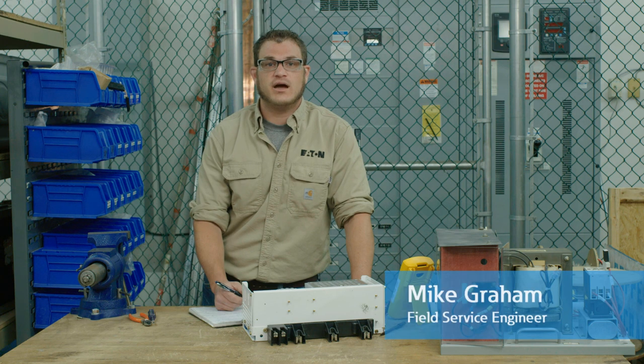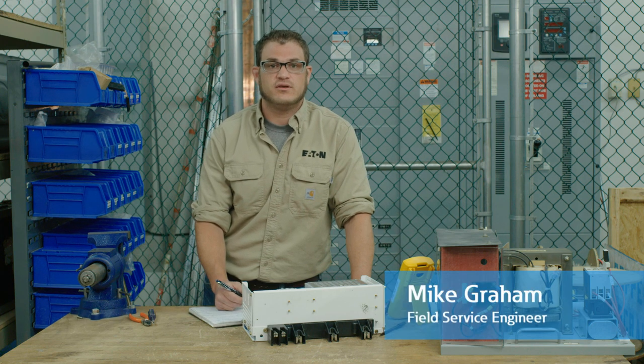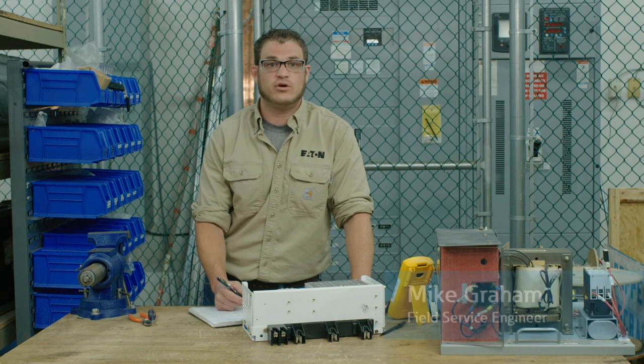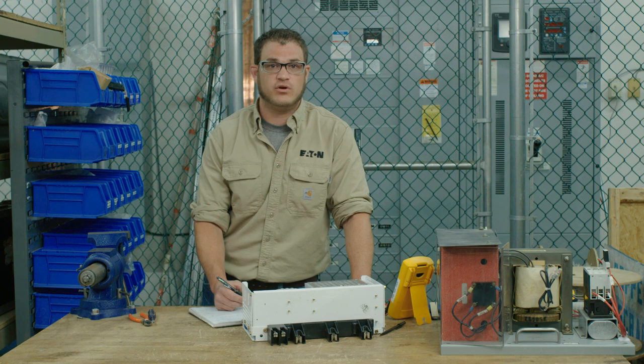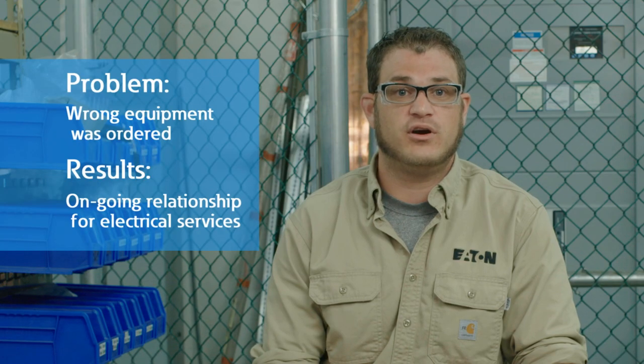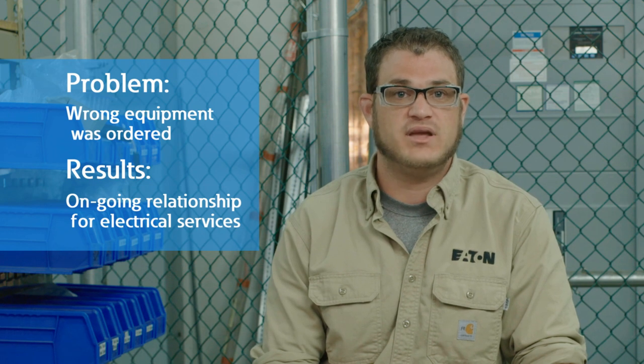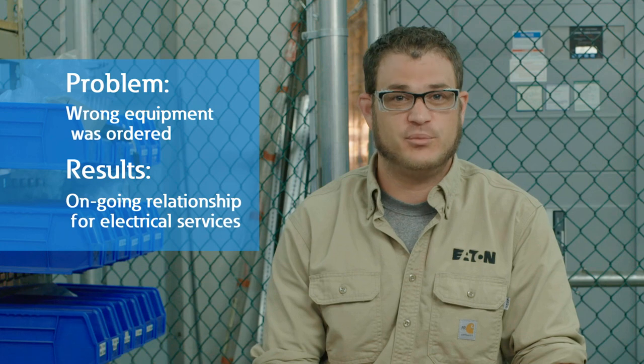As an engineer, we encounter many different types of situations. For example, on a recent startup, we discovered that the wrong relays were ordered and did not offer differential protection. Without this protection, it could have caused serious damage and potential safety issues. We worked side by side with the customer to order and install the correct relays. We were able to meet the customer startup deadlines and turn what could have been a potential problem into success. We now have a great partnership with that customer.